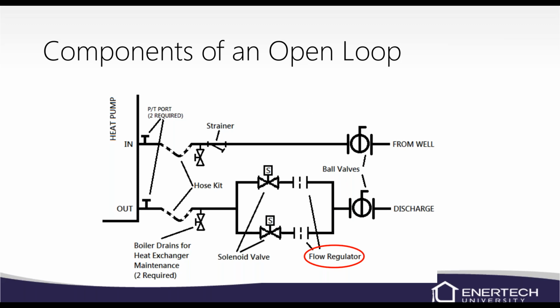You'll have solenoid valves. If you've got a 2-stage unit, then you'll more than likely have 2, one for first stage, one for second stage. Then you'll have some flow restrictors or flow regulators. You'll order those for the specific size of the unit. And then make sure you've got a ball valve on the unit, on the discharge as well, again, so we can isolate some stuff.